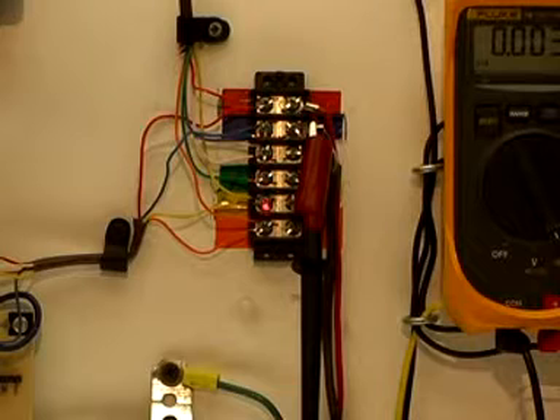So at this point, you've reached a conclusion that there is a short circuit somewhere in the system, which is what caused the fuse to blow or the transformer to burn up. But now you've got to go back and start eliminating possibilities. And in order to do that, you've got to start disconnecting, you've got to start breaking the circuit somewhere, at the failure to begin with.